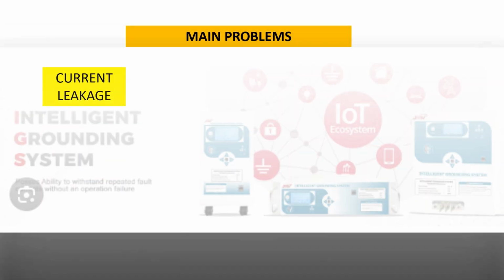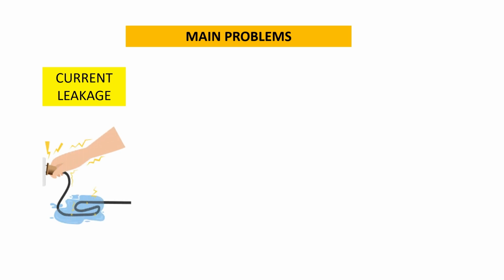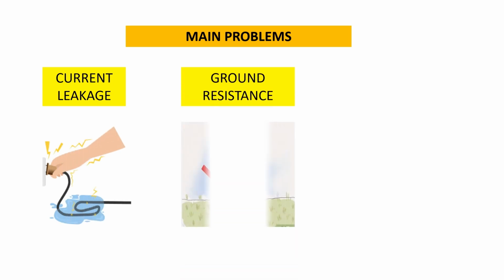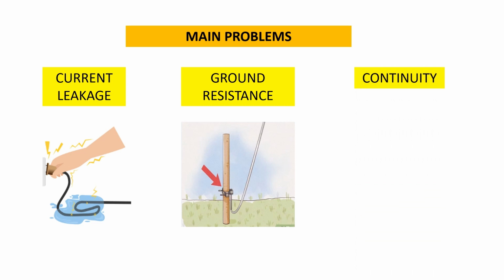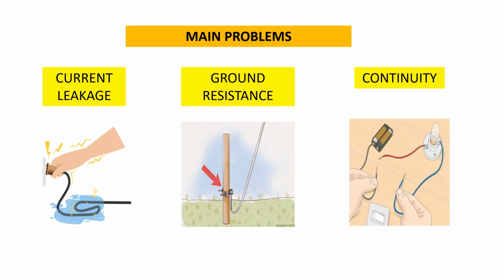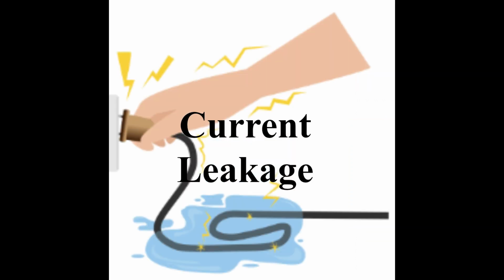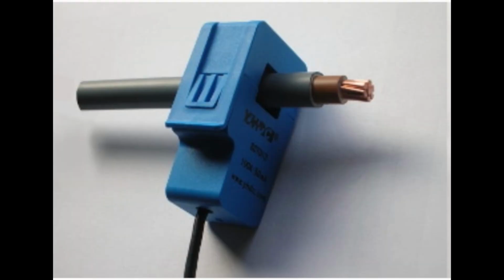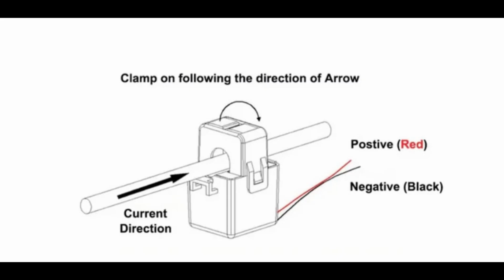Three main problems that need to be checked in the earthing system of a street light are current leakage, increment of ground resistance, and continuity in the system. So let's discuss them one by one. For current leakage, we have used a split core current transformer. A split core current transformer operates on the principle of electromagnetic induction.